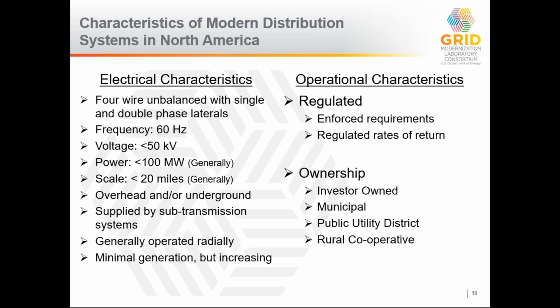Distribution circuits are almost always operated radially. What this means is that there is a single path of power to flow from the substation to each house. That's a very cost-effective way to do it, but there are some reliability issues because if you have a break in there, there's no power. But these can be rerouted manually and sometimes automatically, which I'll talk about later.